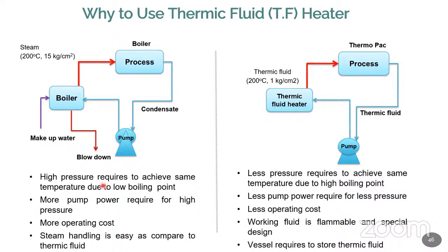The main important point is that high pressure is required to achieve the same temperature due to the low boiling point. More pump power is required, and auxiliaries are higher. You can see there is a feed water pump, a makeup water pump, a condensate water pump. Then you have an ID fan and an FD fan. These are the auxiliaries, and additional auxiliaries are higher in the boiler system. Because of that, more electrical power is required for operating the boiler. So therefore, more operating cost. So the steam cost is going to be very much higher compared to the TFH.